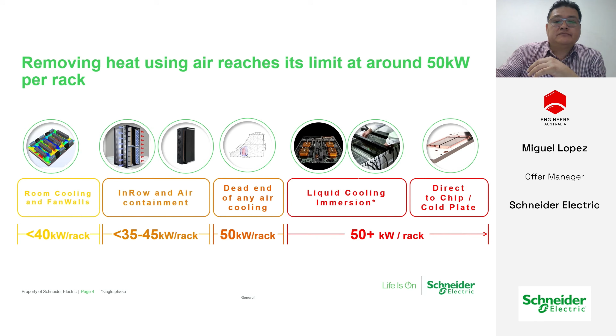As we see in this slide, we've traditionally deployed in-row coolers and containment solutions to boost the effectivity of air conditioning in delivering air to our servers. But we're reaching a dead end at 50 kilowatts. So now the likes of Dell, Lenovo, and other manufacturers are incorporating so-called liquid-cooled, high-performance compute servers, whose heat density now skyrockets in excess of 50 kilowatts per rack. In the next few slides we'll delve a bit into that detail, what that looks like.